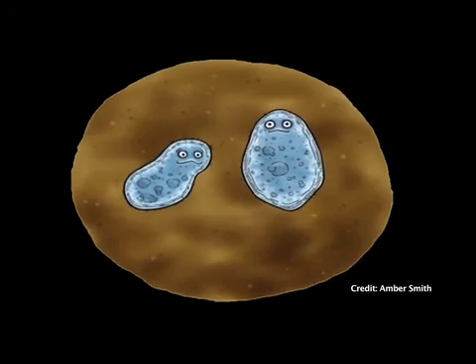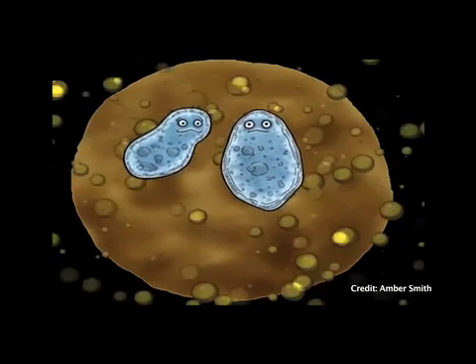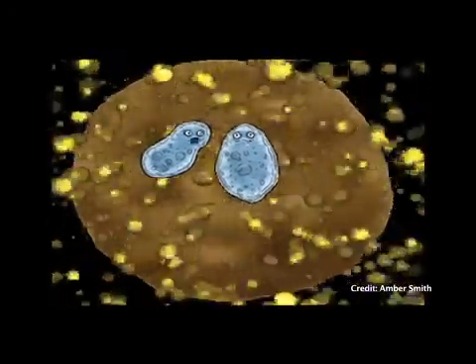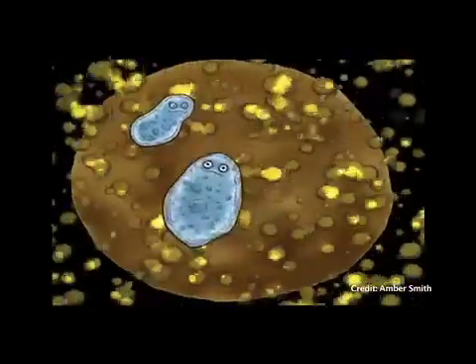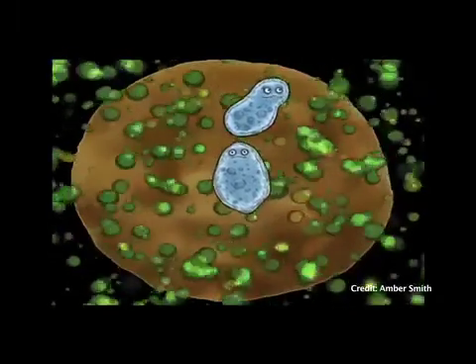You see, these so-called nitrifying bacteria have a penchant for some of the stuff that's up till now been particularly difficult to remove from wastewater. So the nitrifying bacteria that we're going to be growing moving forward break the ammonia and nitrogenous material down to remove it from the system. So there's a nitrogen cycle. It's similarly occurring in plants. That's why manure has nitrogen in it and phosphorus and other nutrients. And so we're trying to remove these nutrients from the water so we don't cause nutrient pollution in the receiving waters and then for our recycled water.